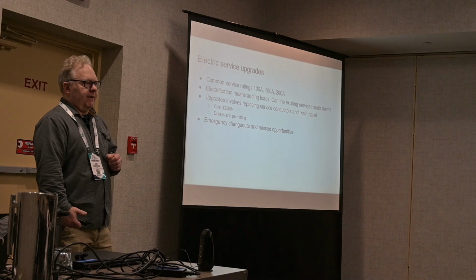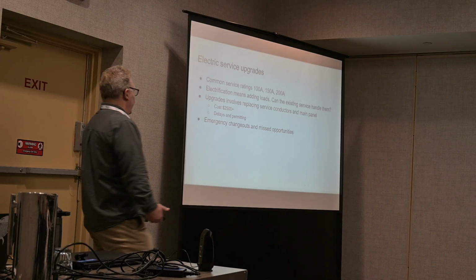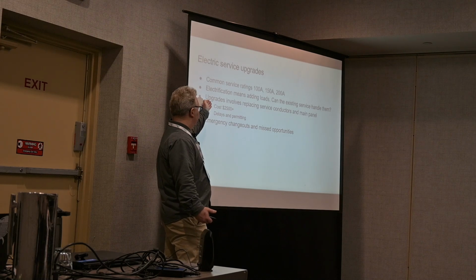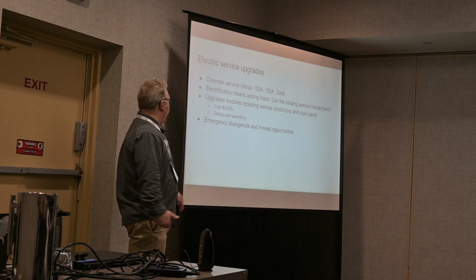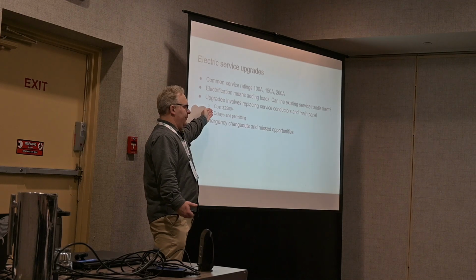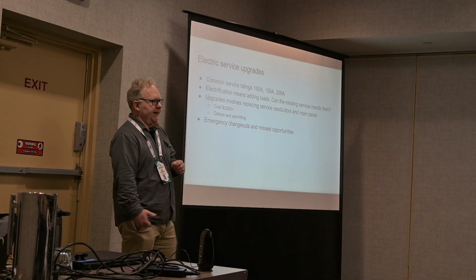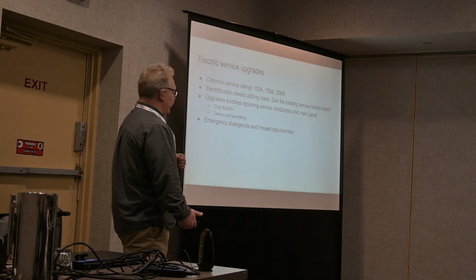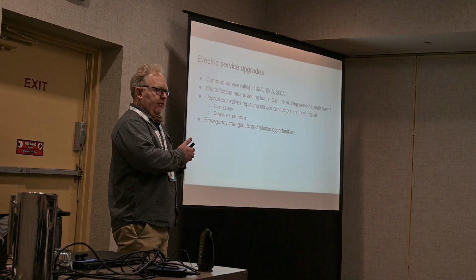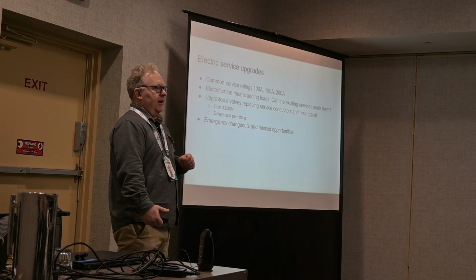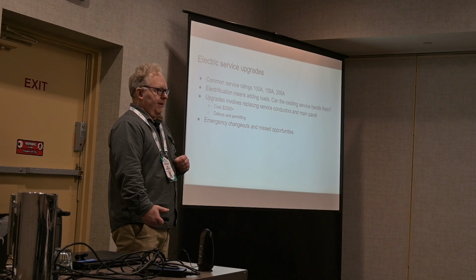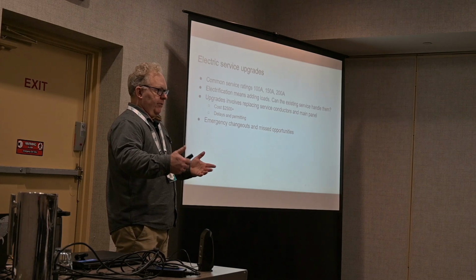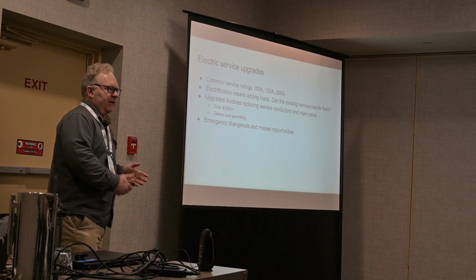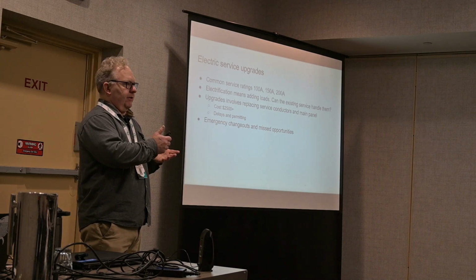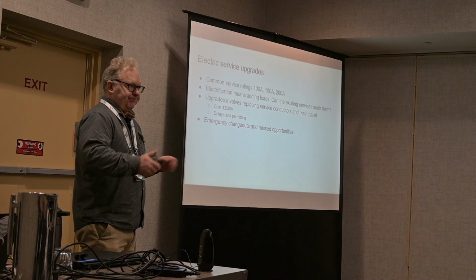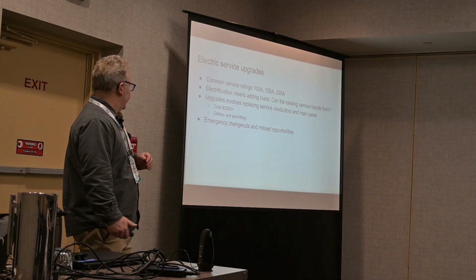But we also want to have some caution in doing this, because upgrading the service can invoke real costs for the customer. I said $2,500 plus here. I think that's on the extreme low end for a service upgrade, and usually it can be more. If you're talking about an underground service that's a good distance from the road, you could be talking about $5,000, $10,000, sometimes even more. And if you have an underground service in an area where it goes under a sidewalk or something like that, it can add additional costs and complications.